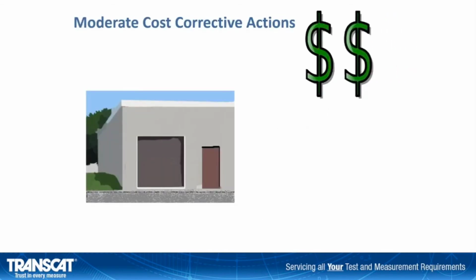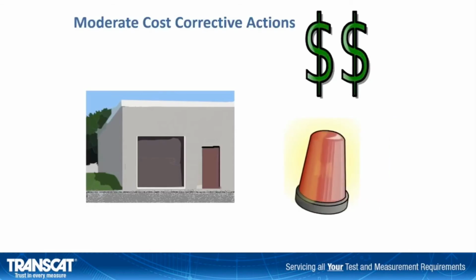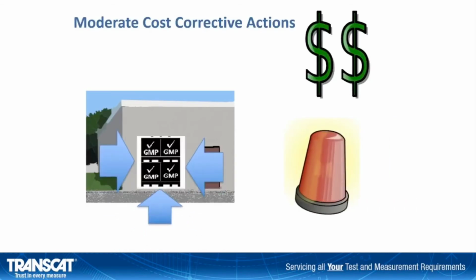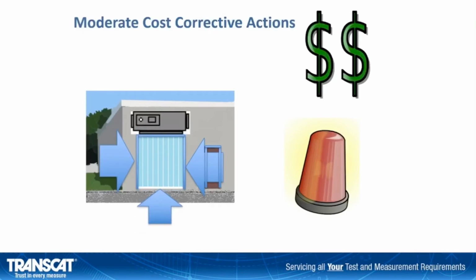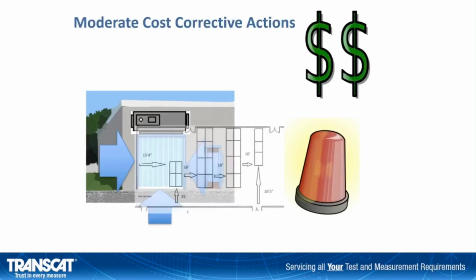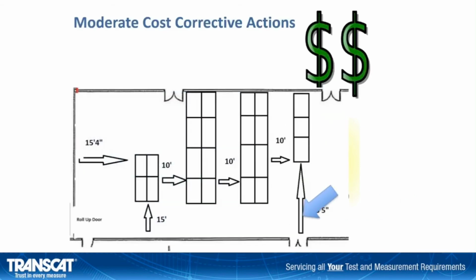Some moderate cost options include installing an audible alarm to raise awareness of open doors. Alternatively, the addition of improved weather stripping or barrier in the doorway can greatly reduce intrusions of outside air. Types of barriers that can be installed include plastic curtains that allow the passage of people and forklifts, installing an air curtain above the bay door. Another method involves isolating the storage location from the shipping and receiving dock by building walls or barriers.